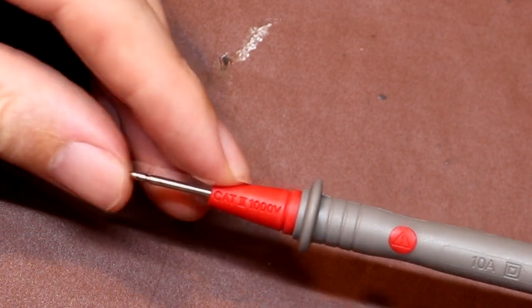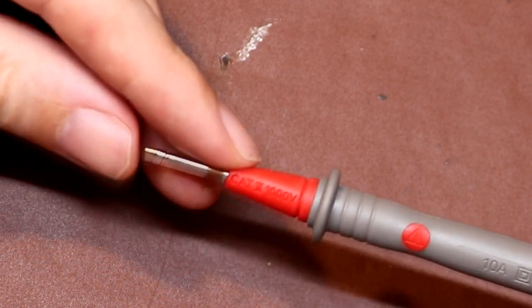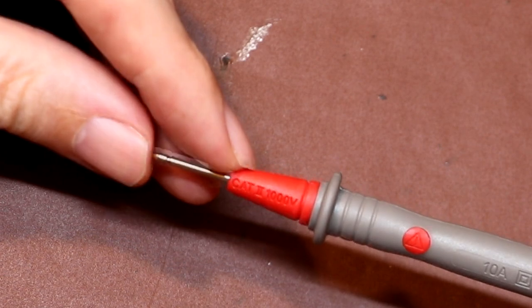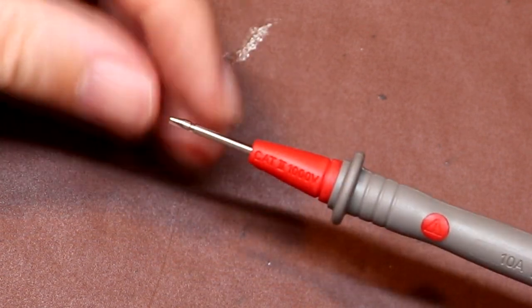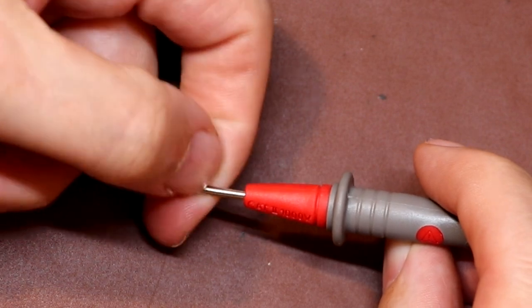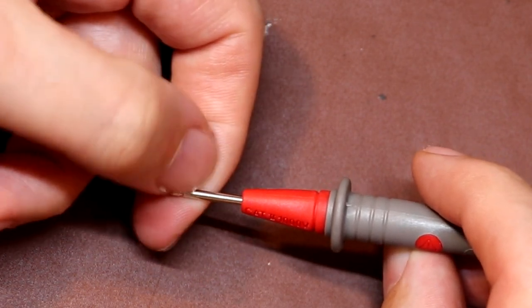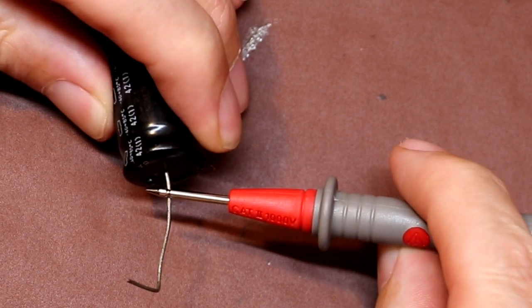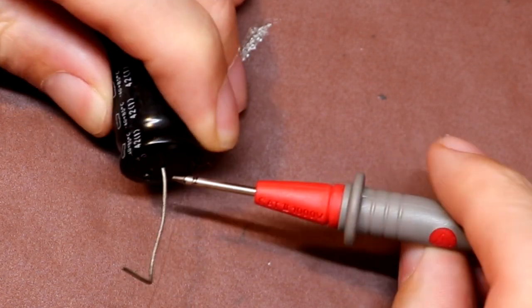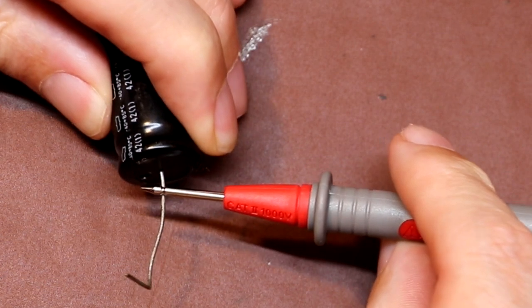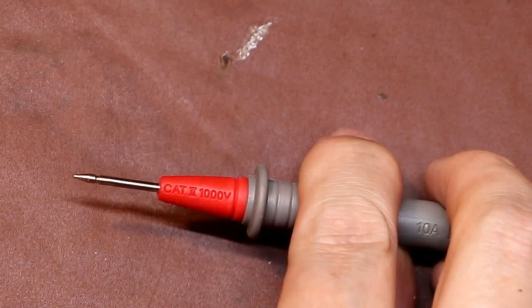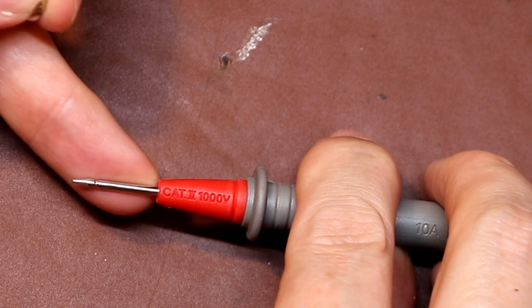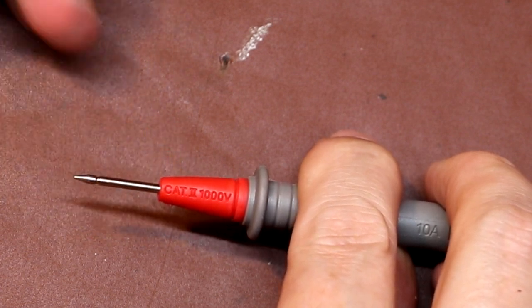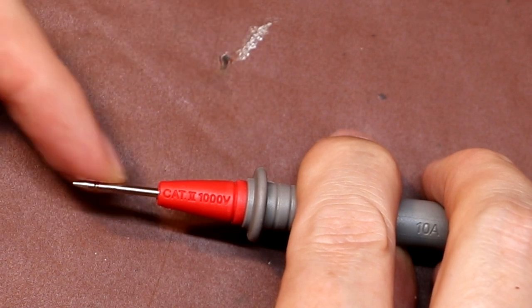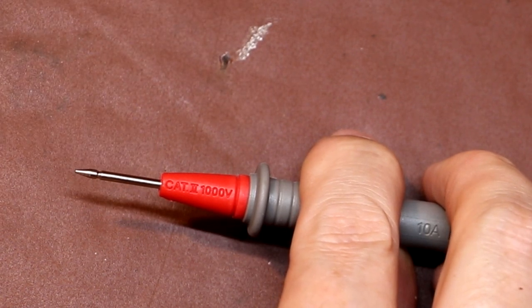So taking a close look at the ouchy part of our test leads, I would say that these are actually, well, they're not very ouchy at all. These are pretty blunt. I would probably like to see these being a little bit sharper than this. Now I can also feel just a little bit of a recessed section on the probe end here. So the idea of that is when you're dragging it along, it will actually seat onto a wire. And yeah, these actually do that quite well, so no problem with that. And taking a close look at the probe material, it appears to be a bright, chrome finish. It's not magnetic, so I suspect these probes are probably manufactured using stainless steel.